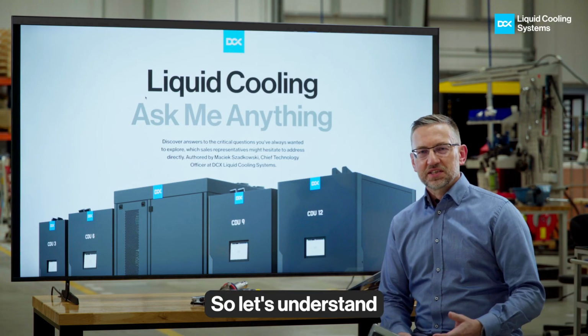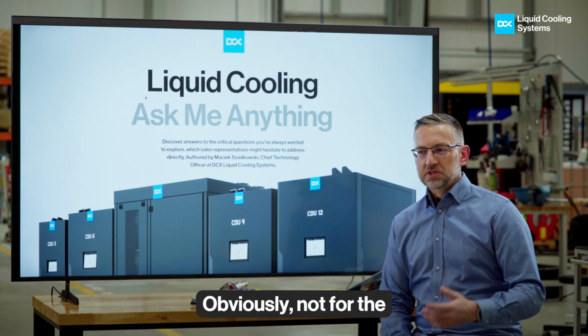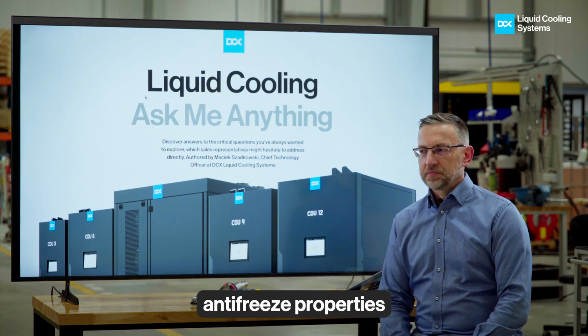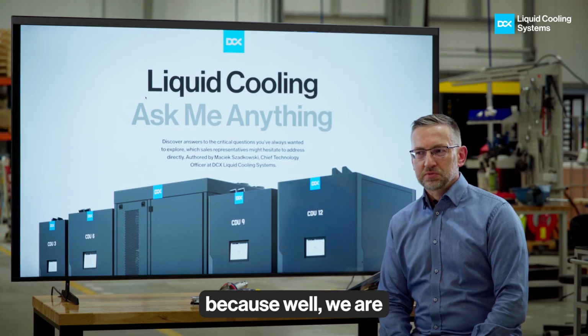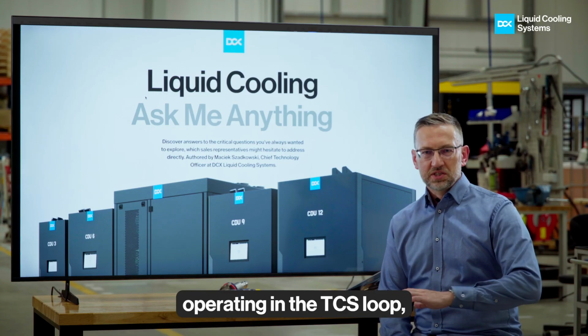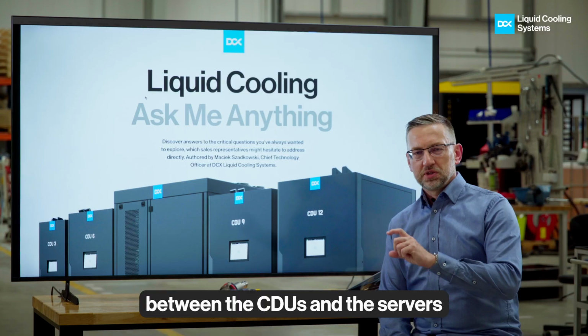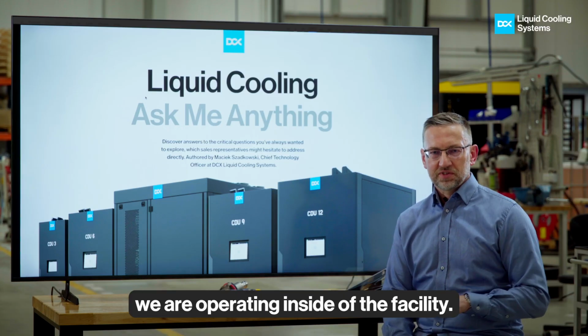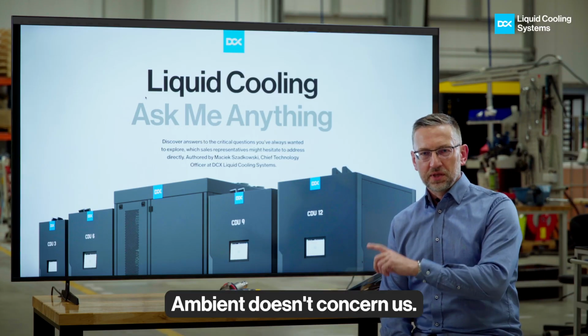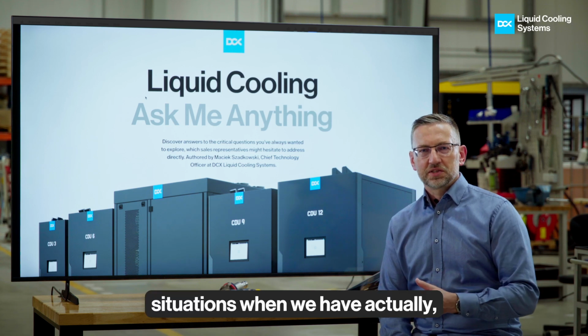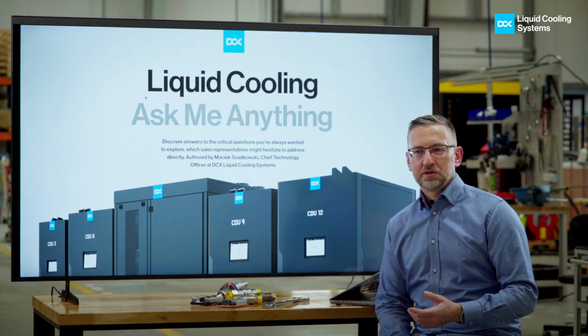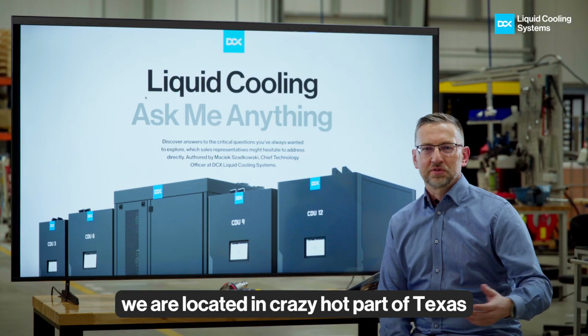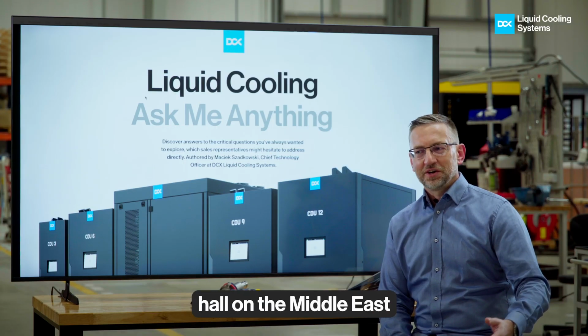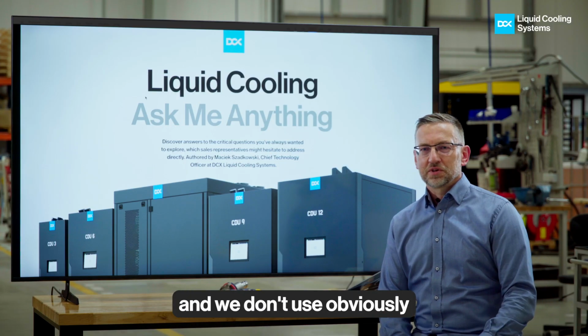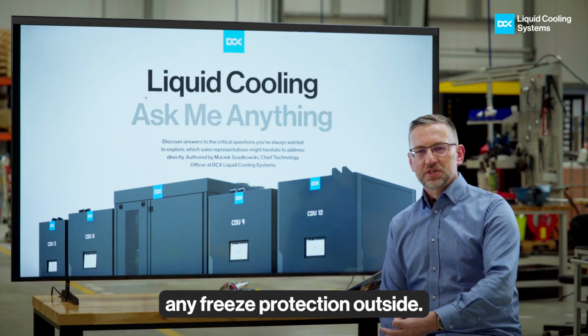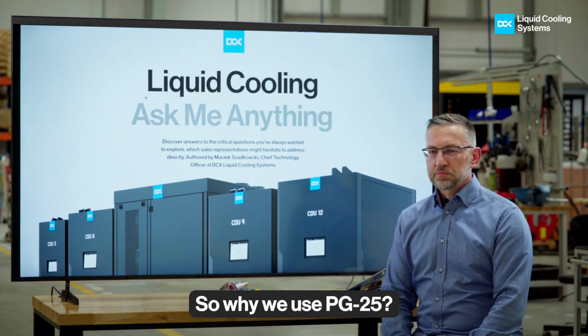So let's understand why we use PG25. Obviously not for the antifreeze properties, because we operate in the TCS loops — a secondary loop between the CDUs and the servers, inside the facility. Ambient doesn't concern us. We've had situations in crazy hot parts of Texas, and in the Middle East, and we don't use any freeze protection outside. So why do we use PG25?